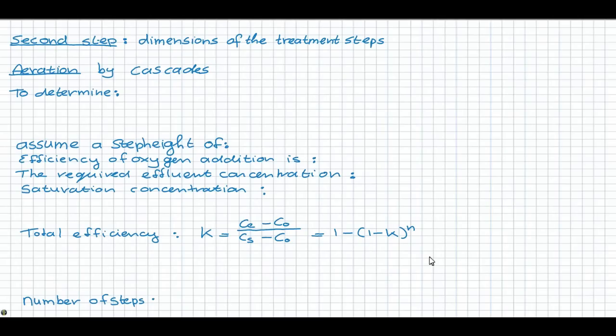The second design step is to estimate the dimensions of the different treatment steps. For the aeration step we choose the cascades, since they are robust and easy to operate. To design the aeration step we need to know the length of the cascades, the number of steps, and the width of the troughs.